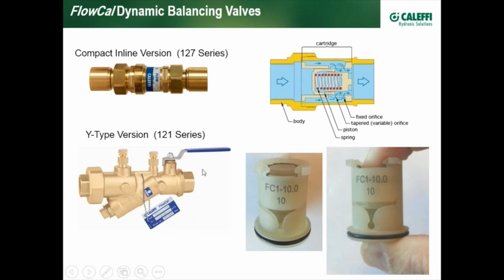Caleffi makes the valve available in your typical Y-type version, such as shown here, 121 series, built-in isolation valve and pressure ports, and then a compact version that has no pressure ports, no isolation valve, and union connections. These are very common for not only hot water, but also some designers like to use them in hot water recirc because they are certified lead-free as well. And they come in your choice of anywhere from 0.5 gallon per minute, constant flow rate, up to 20 gallons per minute.